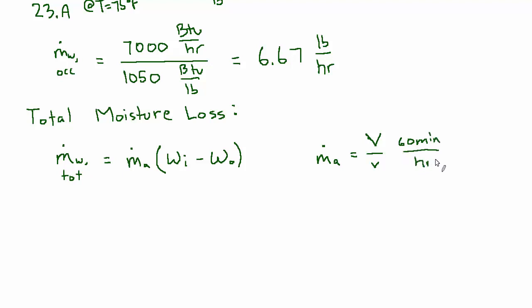So that's fine with the understanding that the exhaust air and the outside air conditions are significantly different because it's very cold and dry outside. So I recommend using the respective specific volumes, little v, that we're dividing by here because the density is so different for those two streams. There's a good chance you can get away with this by just picking one and using it or choosing an average value. Sometimes I'll just use 13 and a half cubic feet per pound of dry air.